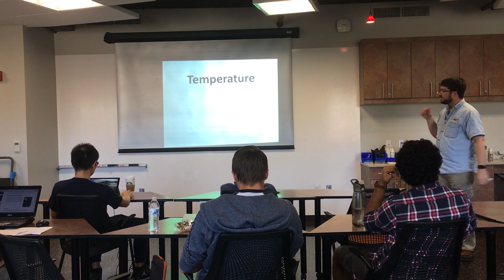Okay, so got to change the title on that, but we're going to talk about thermocouples, RTDs, resistance thermal devices, or resistance thermometer devices, and thermistors. Each of these have a different set of trade-offs that you can get. So for example, if we're looking at the temperature voltage output for a thermocouple, you can see we've got a pretty nonlinear response. Temperature resistance for RTDs and for thermistors are also nonlinear. You can think of the slope of that as kind of the sensitivity. So these are going to have different sensitivities as well, and then they have different costs associated with each of them.